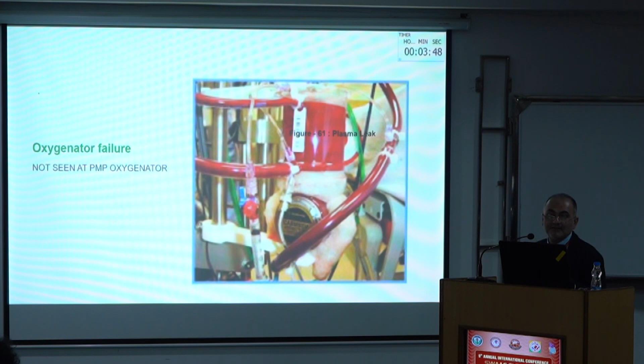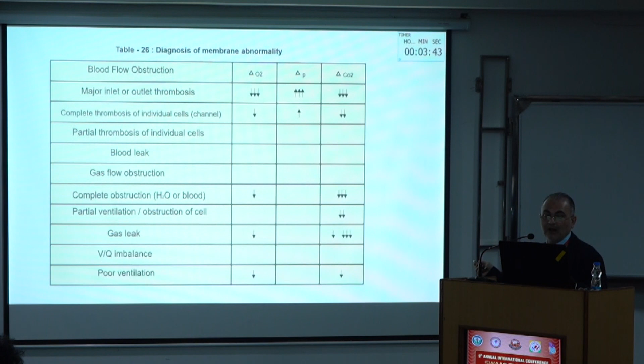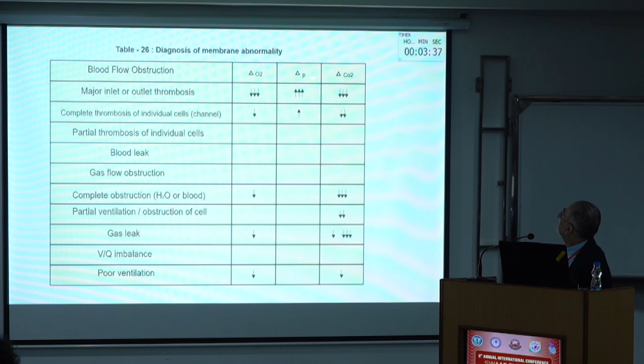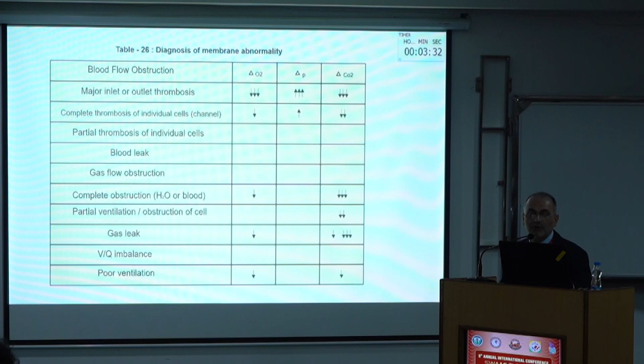You can see here the sign of the hole which comes out of the oxygenator. This is a table that shows you what happens to the delta P pressure and the PCO2 in several types of problem in your membrane. Heat exchanger failure is another one. It mostly happened before, when you had the extra heat exchanger outside the membrane, and nowadays we see such a problem very rarely.